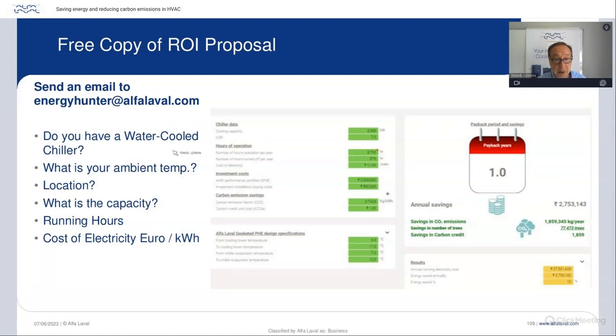energyhunter@alfalaval.com. If it's a water cooled chiller, what is your ambient temperature and the location? We would like to look on the internet how many days you will have temperature under 6 degrees Celsius for your water. Capacity of your chiller, your running hours, and we provide a document like this, which is a proposal with the payback period showing all the values that we have put together so that you can advance with turning the chiller off in that sense.